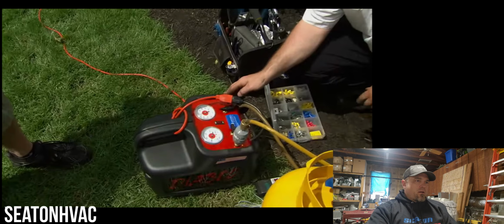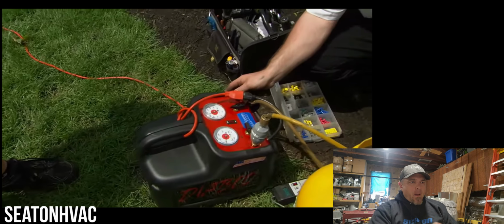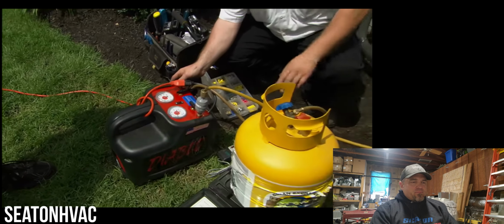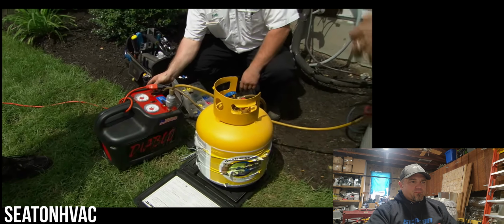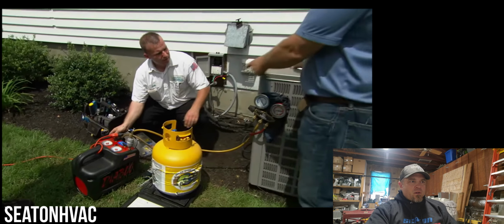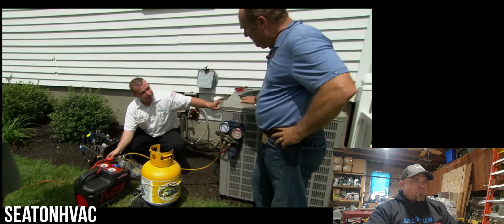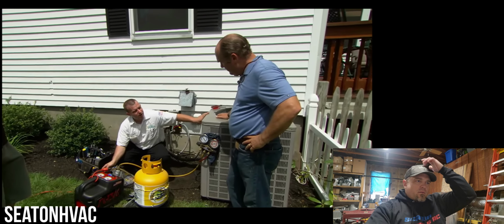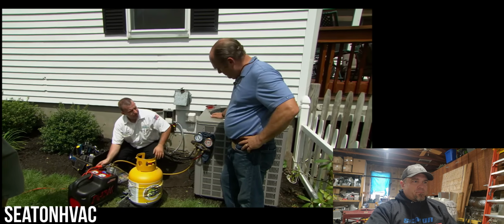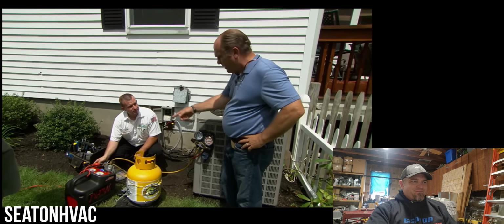So sort of a giant vacuum pump? Exactly. And then afterwards it gets stored into this recovery cylinder. How long will it take to suck all the refrigerant out of this condenser into that canister? Out of this particular unit, 20 minutes to a half hour, or until both of these gauges are at 0. All right, you ready to go? Yes, I am.